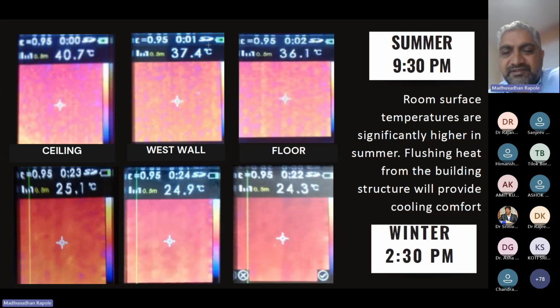Now, this journey does not happen in one day. Unfortunately, most air conditioning professionals do the heat load as an instantaneous problem, not a time series problem. Of course, ASHRAE has clearly specified that the radiant time series method is the way to actually quantify the heat load, because then you are taking into account the residual heat from earlier instances. But that is not how we do it, we don't consider it. So if you see the journey from here to here, it will be half a degree, 0.75 degree getting added every day. So by the time you come to March or April, these will be the temperatures.